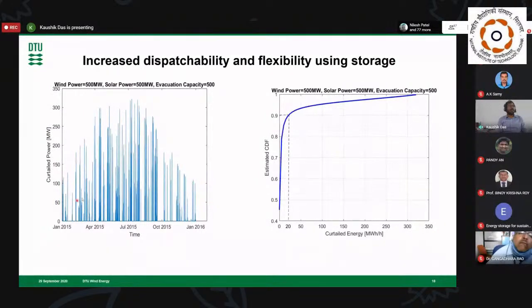Then we started plotting the curtailed power - not energy, but power - and developed a cumulative distribution function, the CDF. We see that 90% of this curtailment is less than 20 megawatt-hour per hour. That means if I put a storage of 20 megawatt, with 1 hour of storage I can capture 90% of this curtailed energy. This also shows the value of storage, or increased dispatchability through storage.